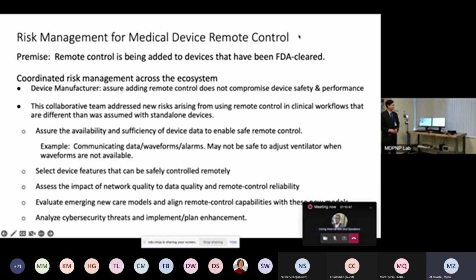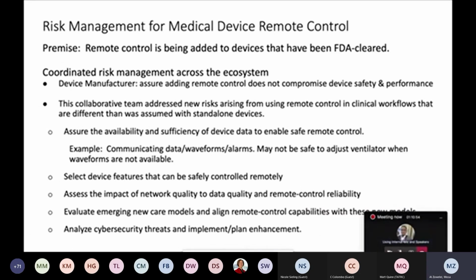Then we have to assure the availability and sufficiency of device data to enable safe remote control. For example, most physicians, most clinicians, respiratory therapists in particular, would be very hesitant to change the settings on a ventilator if they could not see the real-time waveforms from the ventilator, the airway pressure waveform, flow waveform, etc. For other devices, it may not be critical to see all that data. And so you have to really think through the purpose of the device and its changes, and also the risk-benefit ratio of what you could see. Now, do you have to see those waveforms on a smart display of some kind on a computer? Well, not necessarily, because as we pointed out, you could look through the window if you're doing this from right outside the patient's room. But if you're doing it from far away, certainly there has to be a way to see the data if it's essential.